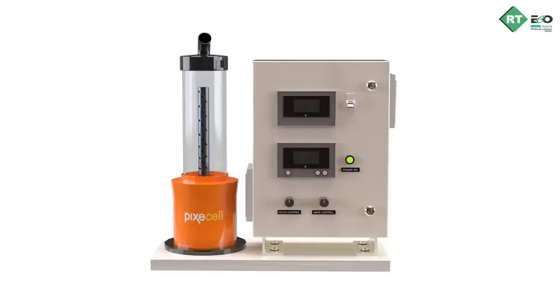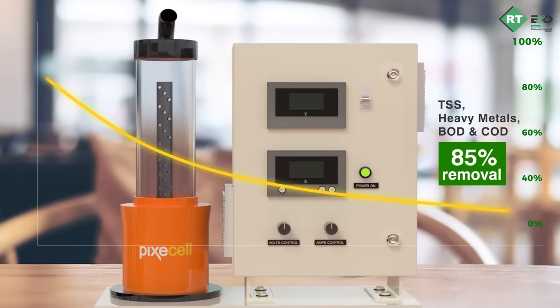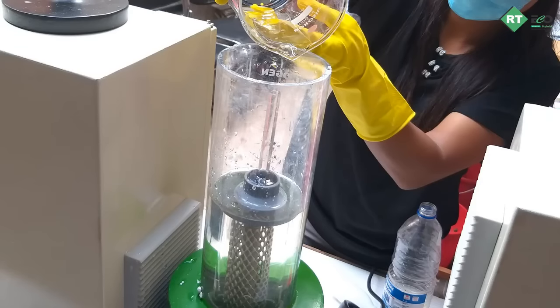The effluent is reacted in our electrocoagulation reactor, the pixecell. Electrolysis of the effluent in the reactor ensures free flow of electrons, destabilizing the surface charges on suspended solids, heavy metals, and organic compounds, forming large flocs that finally settle down — providing a clear liquid with 60 to 85 percent removal efficiency of TSS, heavy metals, BOD, and COD.